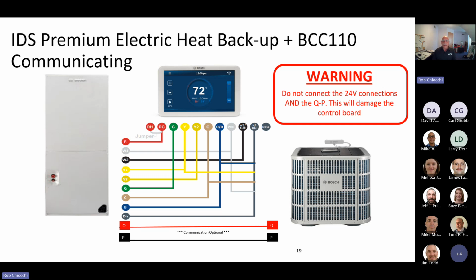You can now connect that BCC 110 in a digital communication scenario utilizing 2 wires between the indoor unit and the outdoor unit. Little warning here is if you choose to do that, you never want to hook up the 24-volt wires to the outdoor unit. That will damage the control board.